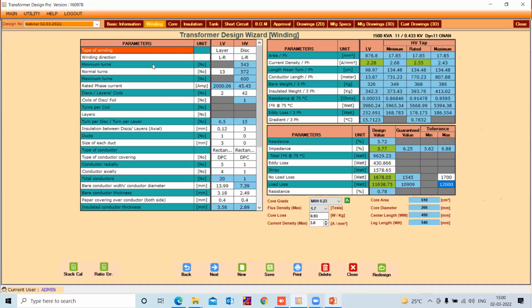So let's look at the parameters in the table on the right hand side. You can see the type of winding. For LV, it has chosen layer winding. For HV, it has chosen as a default disc winding. But is there any other option to decide or change this? Let's click on that and see whether you are in a position to change. Yes. For HV, you have layer option. You also have the crossover option. For LV, let us see what are the options it provides.